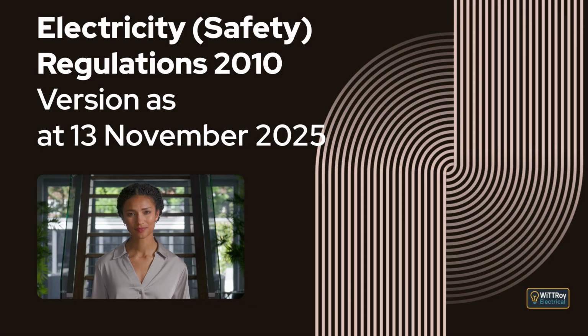We'll now look at certified designs for installations. Reg 58 Certified Designs. This regulation explains what a certified design is. A design is a certified design if it identifies the location or proposed location of the installation or part installation, identifies the standards that the installation complies with or is intended to comply with, and is signed and dated by the person who prepared it.